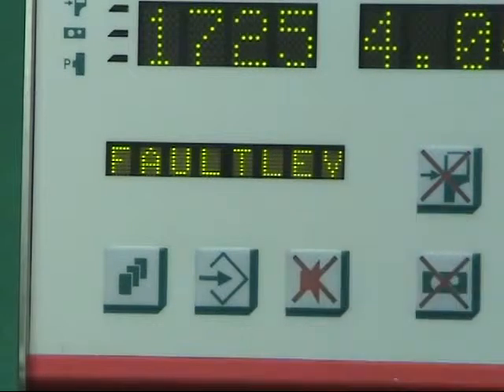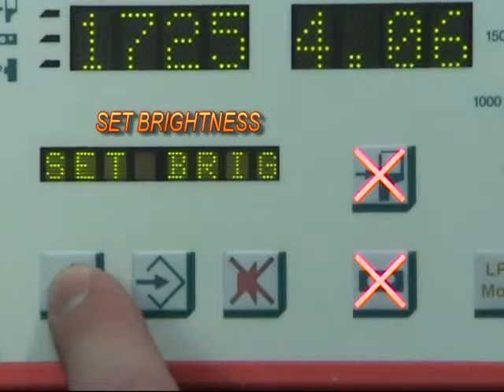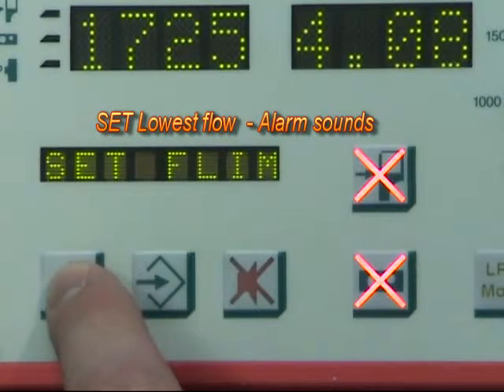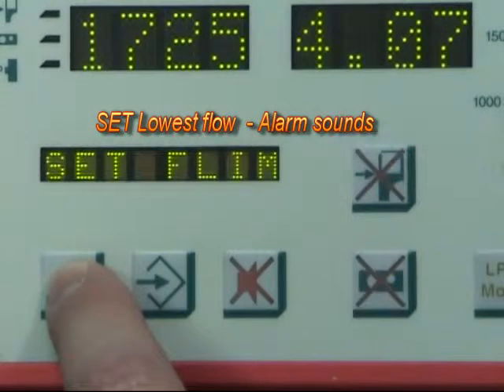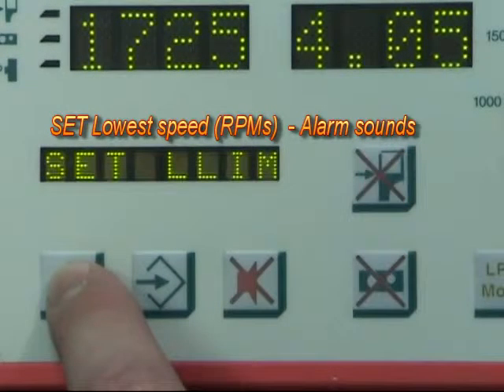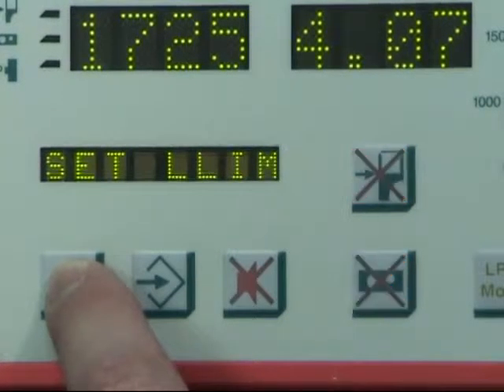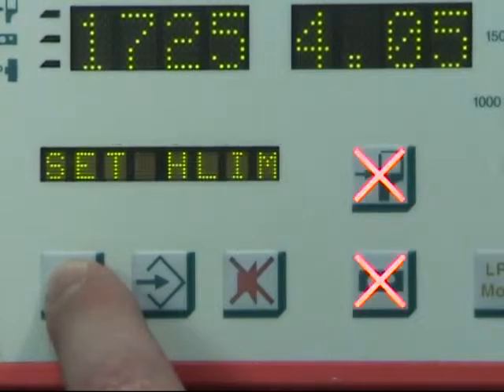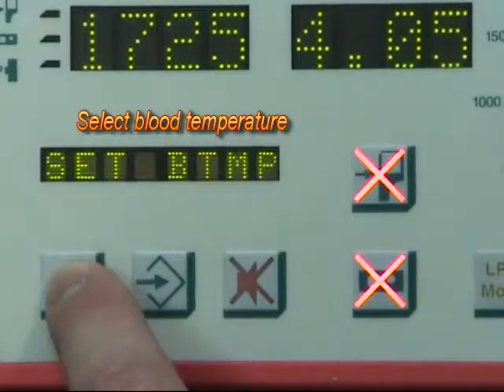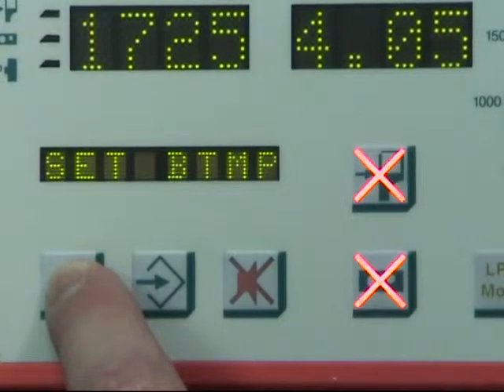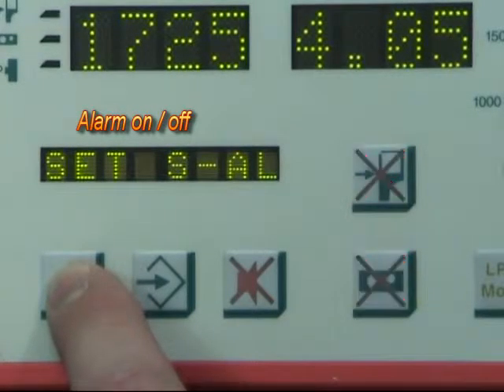Remaining menu items are as follows. Set Bright selects the display brightness. Set Flim selects the low flow. Set L lim selects the lowest speed in RPMs. H lim selects the upper speed in RPMs. Set clamp is not used. Set BTMP selects blood temperature. And set SAL selects between alarm on and off.